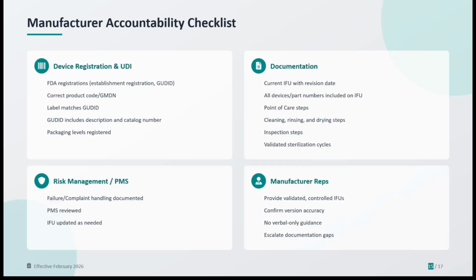For documentation, they should be current version and include every device or part number it applies to, along with complete point of use, cleaning, inspection, and sterilization steps based on validated cycles. For risk management and post-market surveillance, it should be visible through how manufacturers handle complaints, failures, and IFU updates. For manufacturer reps, you should expect controlled IFUs, verified versions, and no off-the-record instructions. That's what ISO 13485 asks of them.